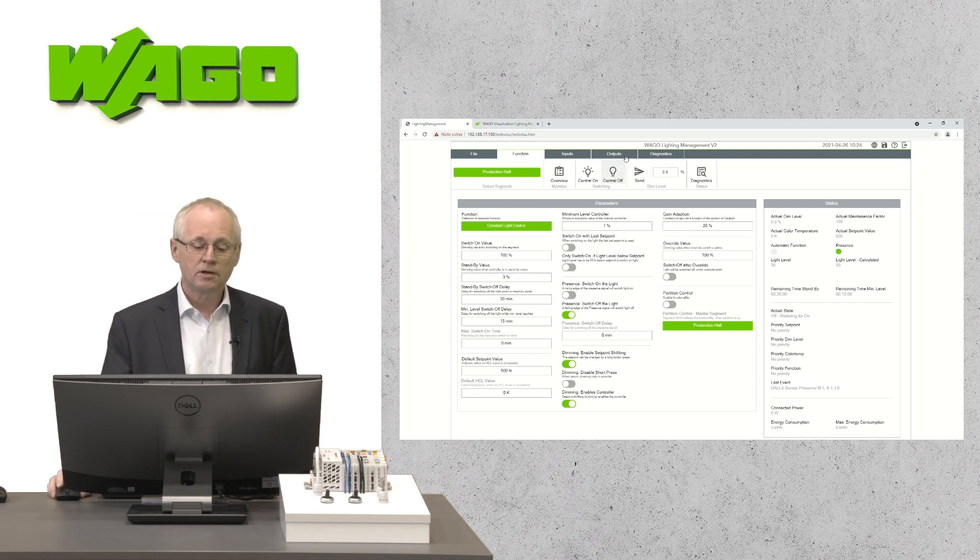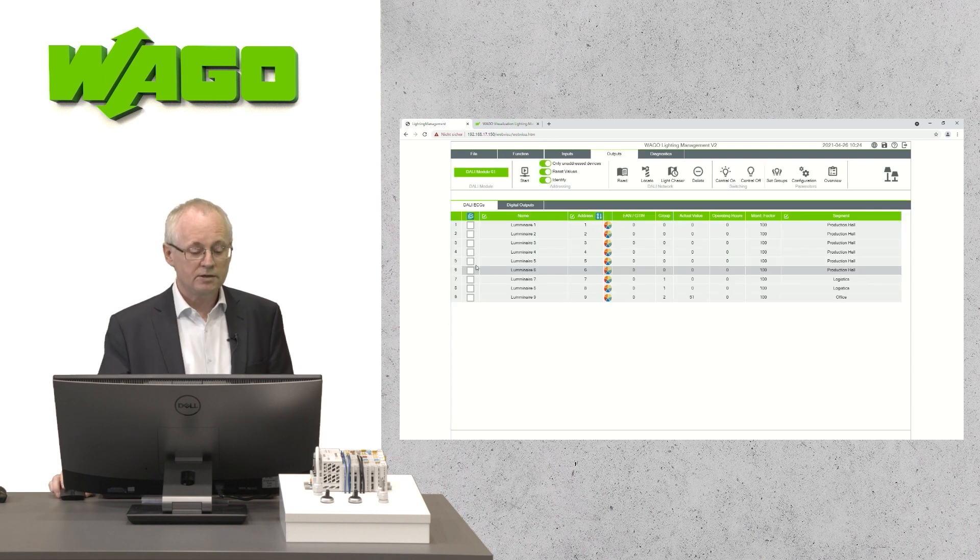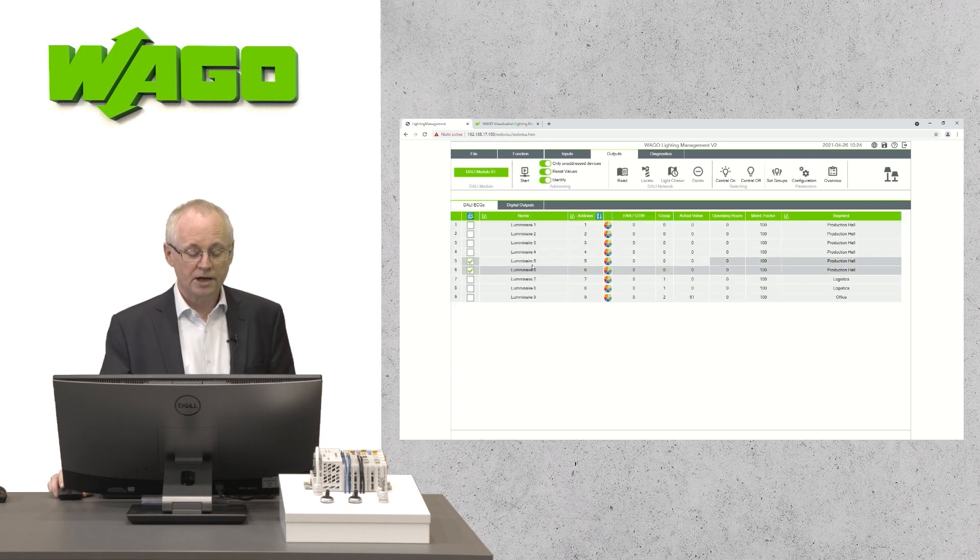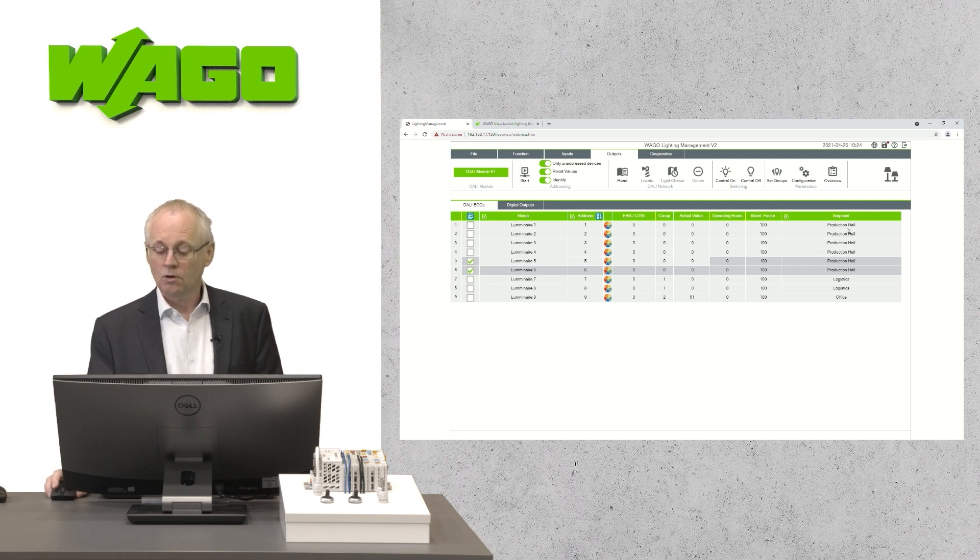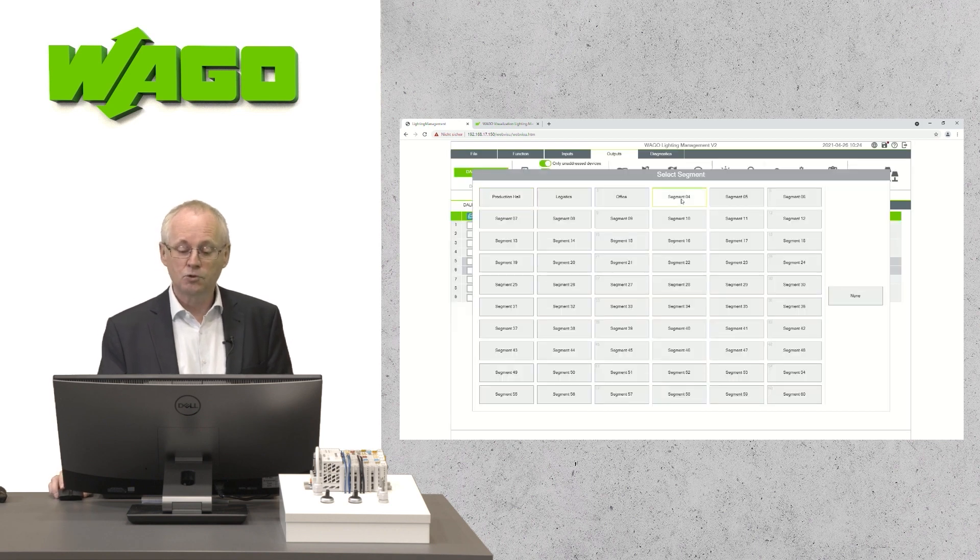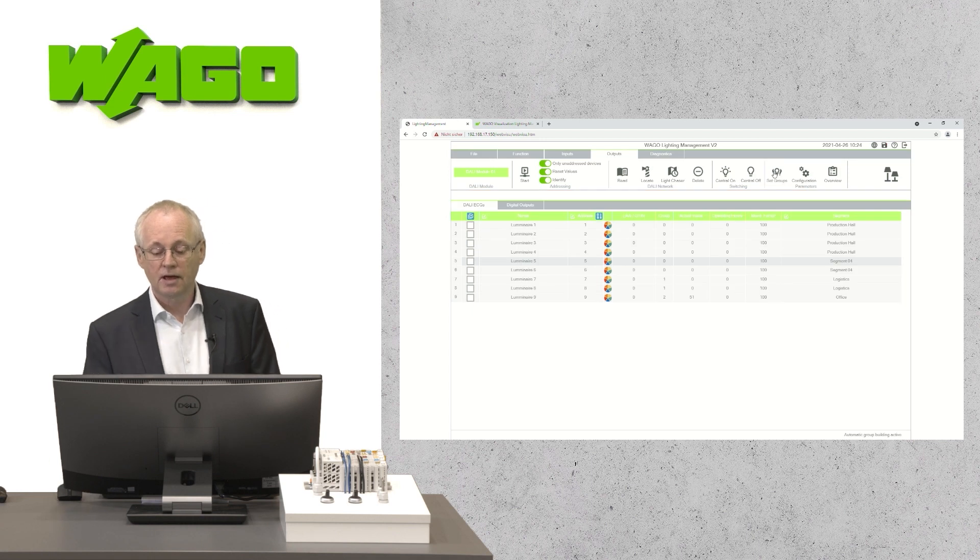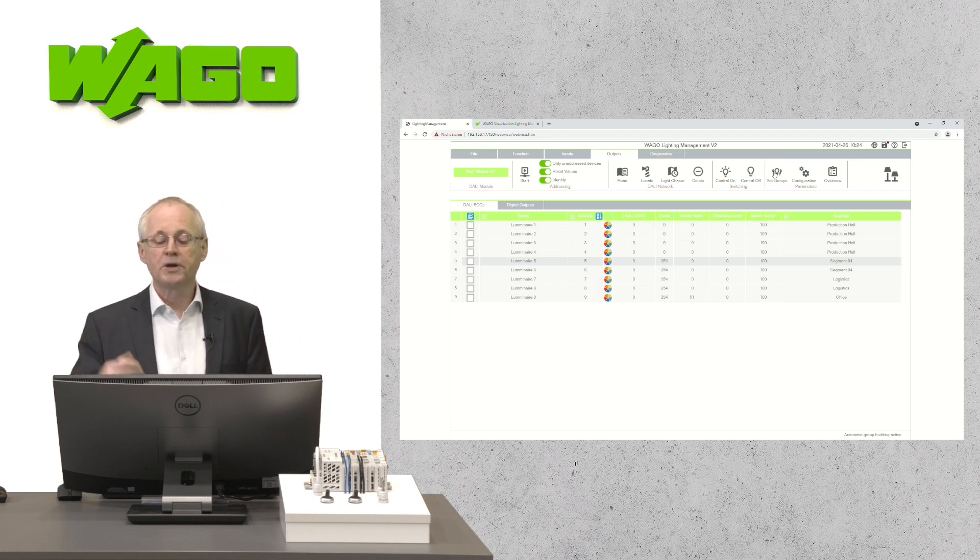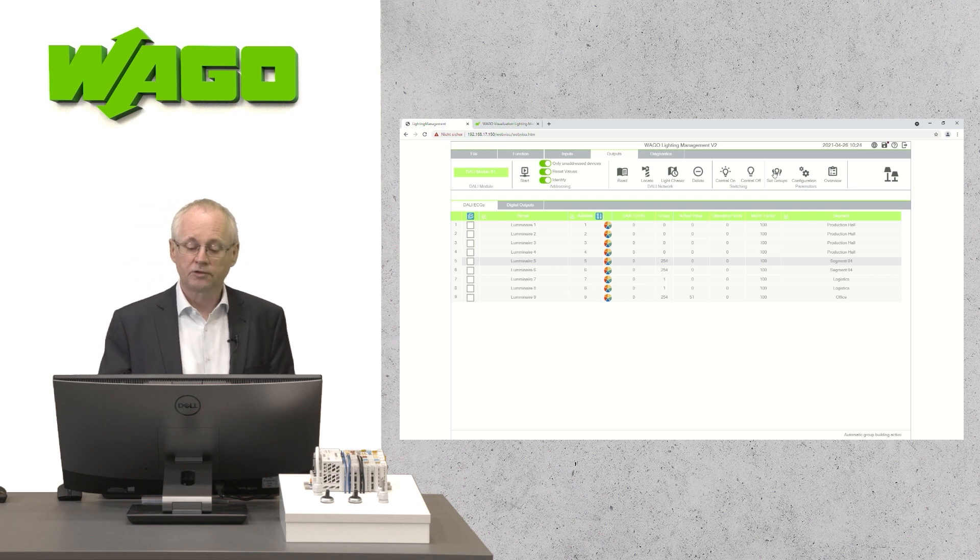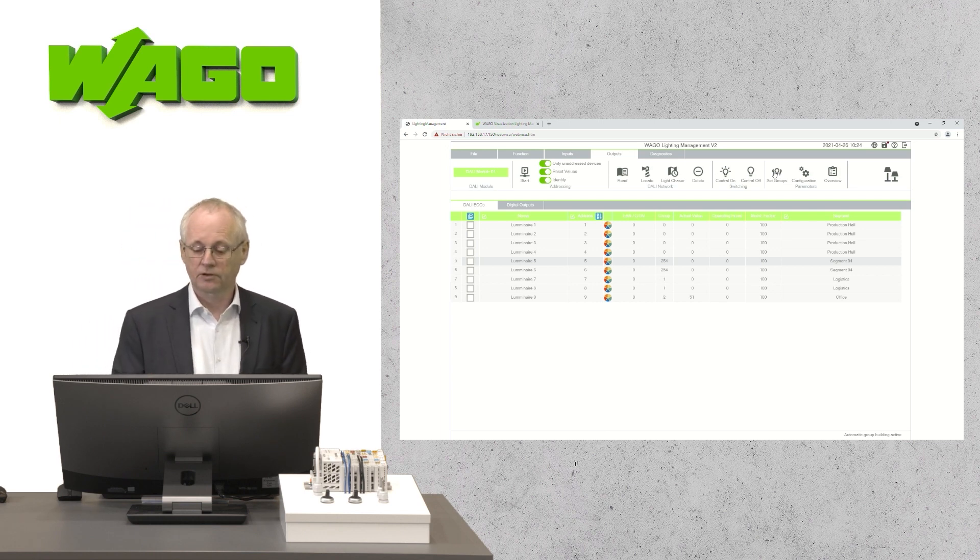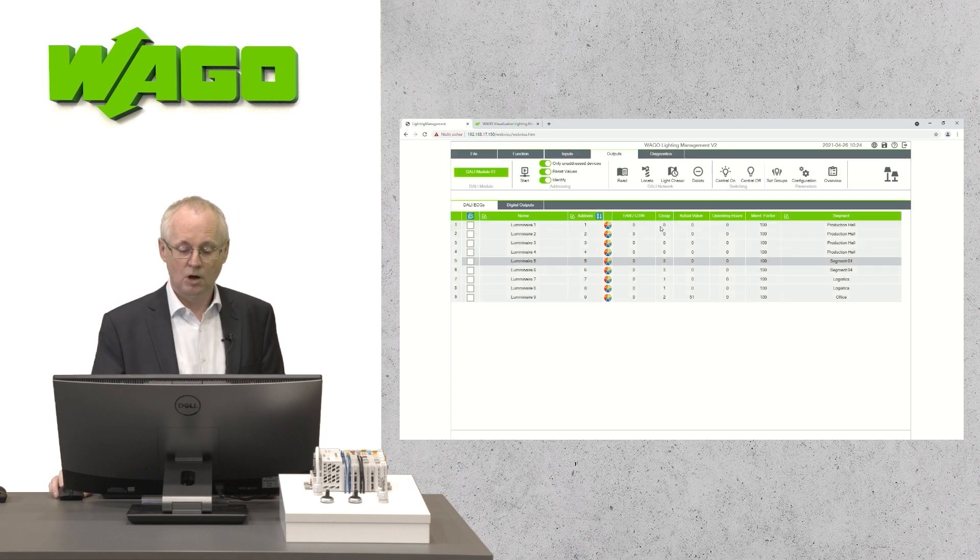Therefore, we will switch to the tab outputs. We select two luminaires. You see that there are six luminaires assigned to the big production hall. Now we select two of them and assign them to a new segment. After that, we need to start the grouping functionality. That is important to transfer this grouping information to the DALI electronic control gears. That takes a while and now it's done.